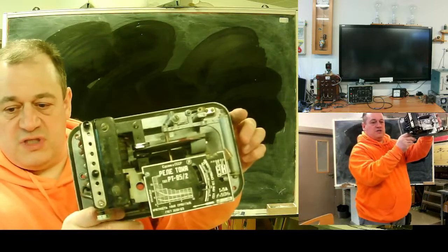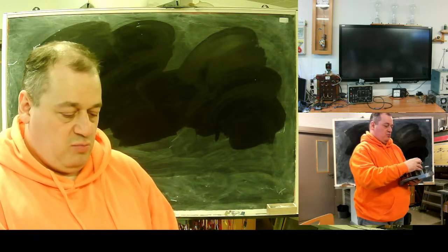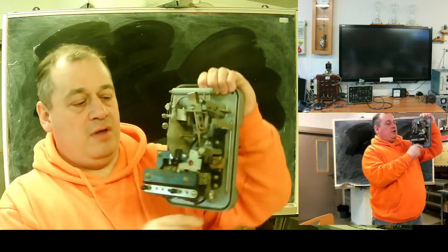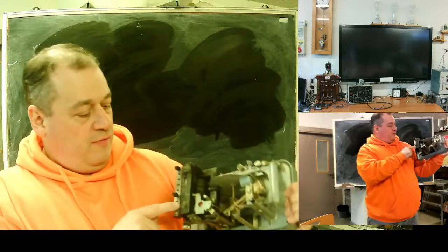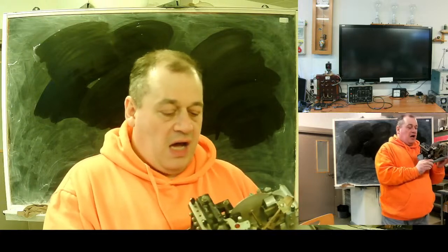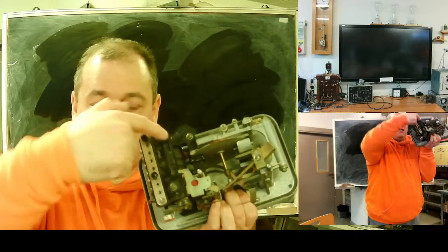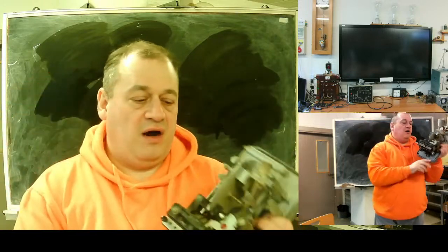Here is the old school solution for this problem, called an induction relay. Old school solution. I will remove the scale. So what's inside? A coil, here. A coil with taps. I can choose which tap to use. This coil has a magnetic core here. It's a magnetic coil, and in the gap of the coil we have this disc, an aluminium disc.